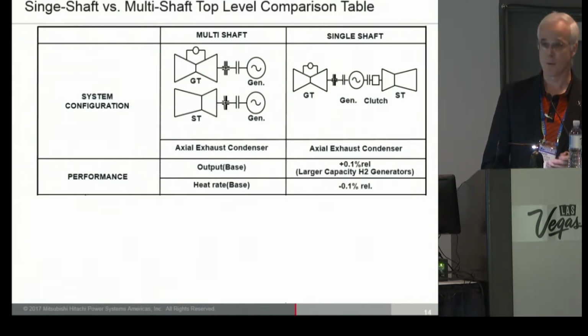If we take a look at performance, typically overall compared to a multi-shaft, the single shaft has about a 0.1% better performance. That is mainly driven by the generator, as one big generator will be more efficient than 2 smaller generators.